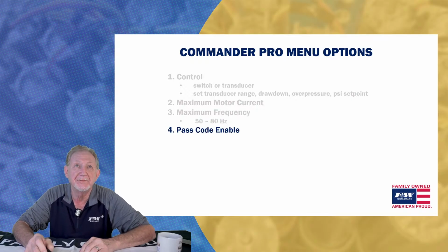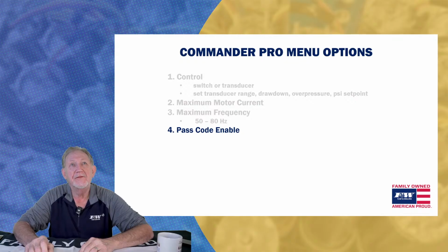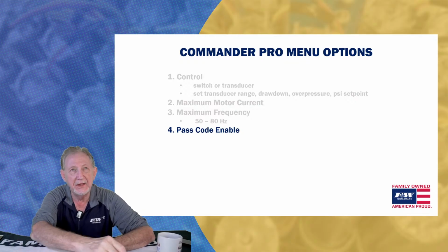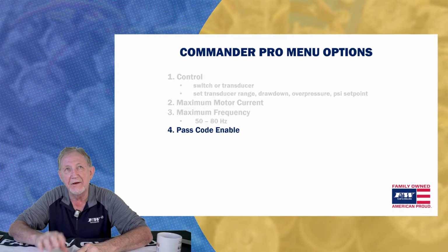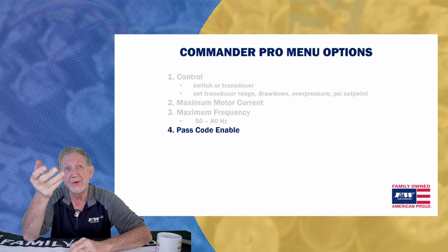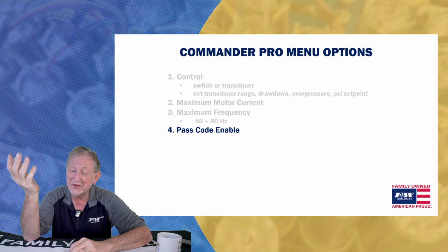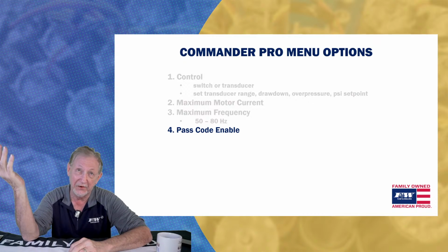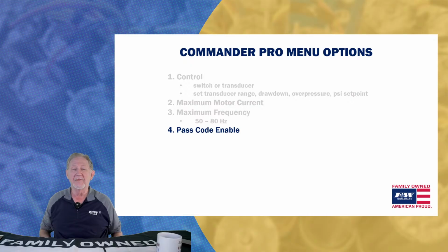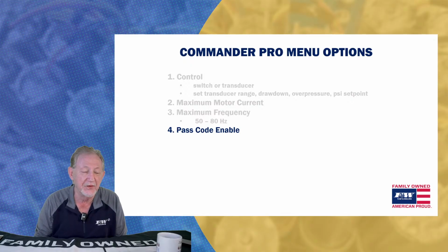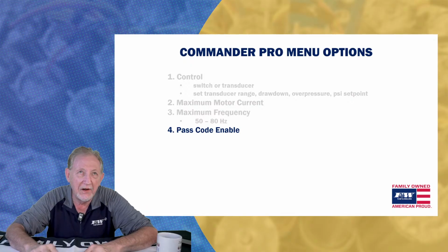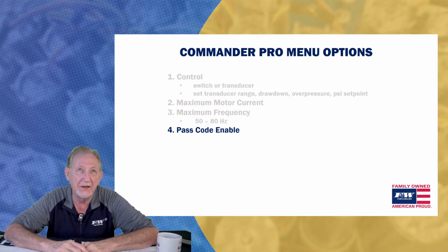We talked about this a few minutes ago, the max frequency can operate anywhere from 50 to 80 hertz. 80 is for mismatched pump and motors, and 60 hertz for all pump and motors that are matched. Menu number 4 is passcode enabled, a neat little feature. You can plug in a 5-digit passcode so that once you hit the edit and enter button, it's going to prompt you for a passcode to go any further. That's a way of protecting the drive so that you don't have any inquiring minds getting in there and possibly changing something.